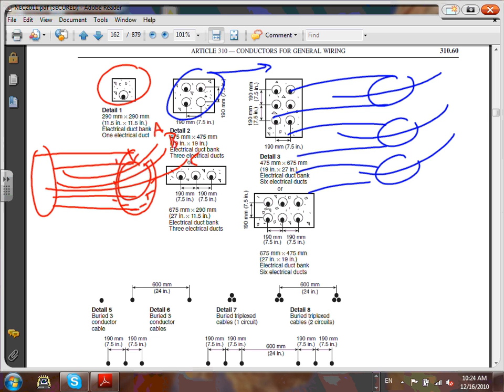I don't think they make a 500 kcm multi-conductor cable, medium voltage. That would be that big. So what do you need to do? They make a single conductor cable, 500 kcm, no problem. So then you use the detail, one cable per dot, one cable per dot, one cable per dot. And if you read through it, sometimes that detail is used also for multi-conductor cable, 3 parallel circuits. So for the most part, for you guys, you're most likely right in this application here.